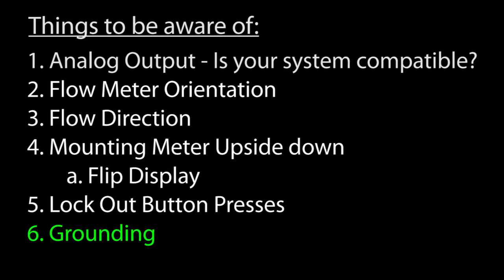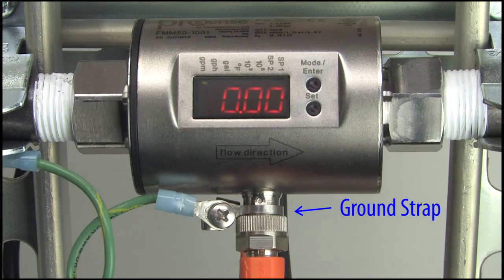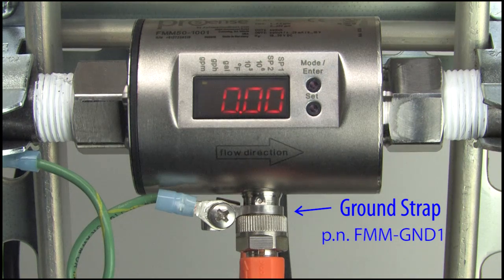This is a class 3 device so the power supply doesn't have to be grounded, but the flowmeter itself does need to be grounded. So if you put this inline in a PVC pipe system, be sure to run a ground wire from the unit. AutomationDirect has a convenient ground clamp for this if you need it.